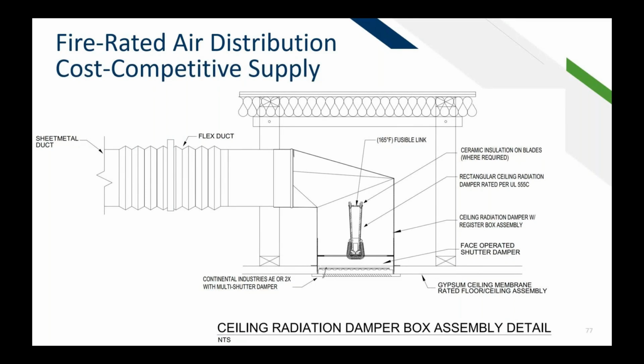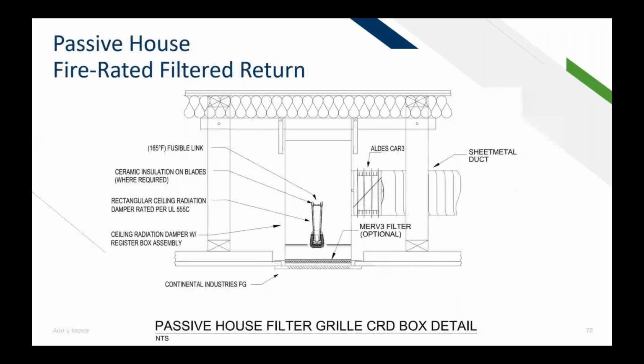So one more thing that's kind of related to Passive House. In Passive House design, you need to have a filter grill in the kitchen, and it's kind of tough to find a filter grill in the kitchen with constant airflow and within a CRD boot to keep it all UL compliant. But that's exactly what this does, and it does it in a pretty cost competitive way. It has the Continental Industries FG2 in the front, which FG2 refers to having that MERV 3 filter that's required by Passive House. And yeah, this is just a good way to satisfy your code compliance in Passive House.